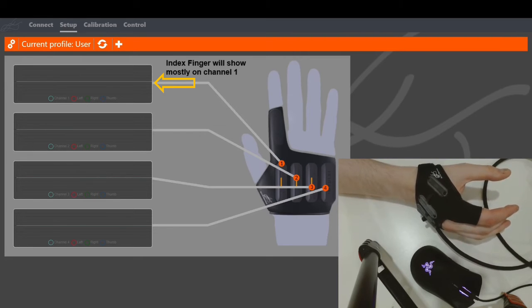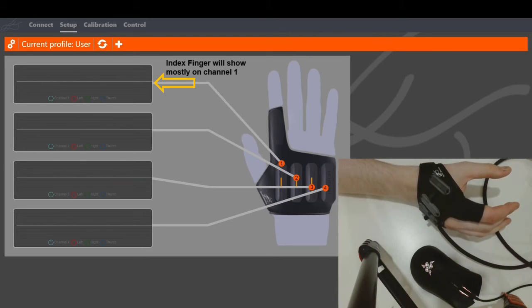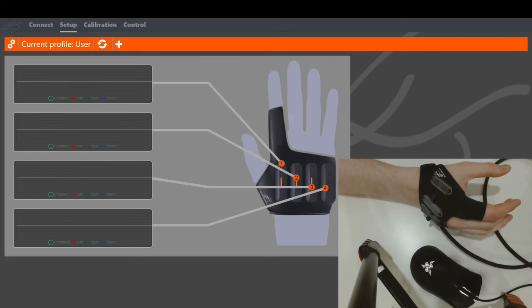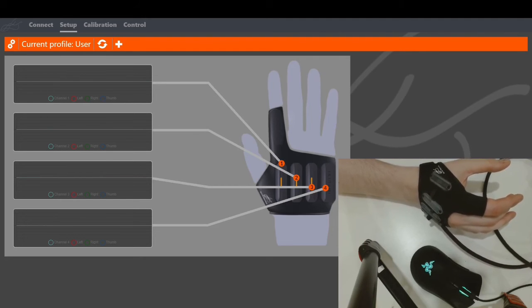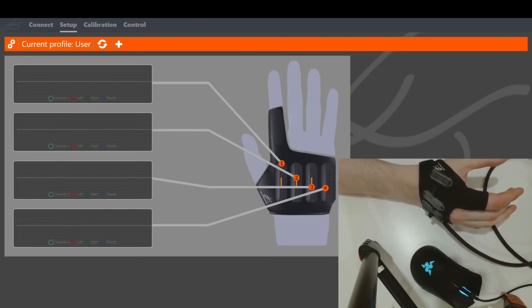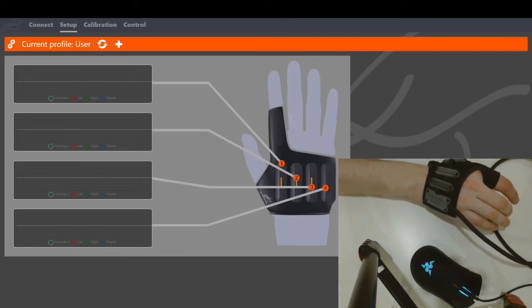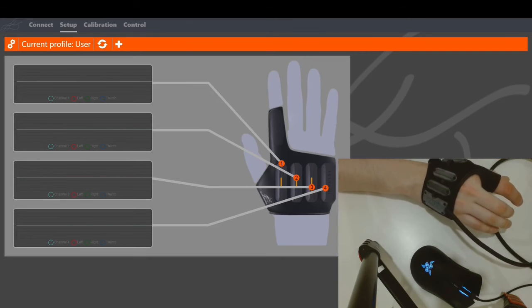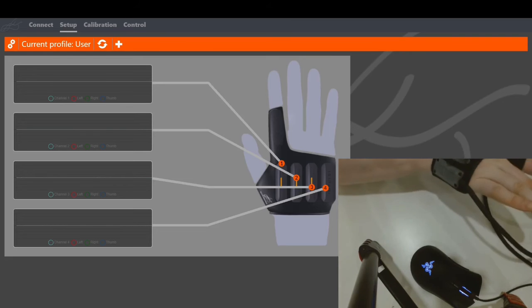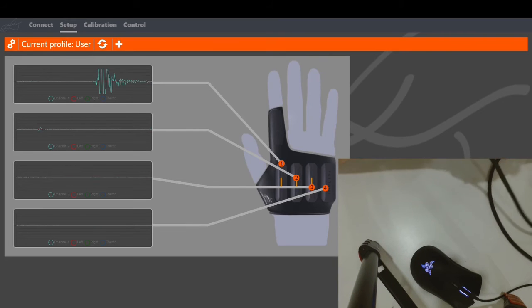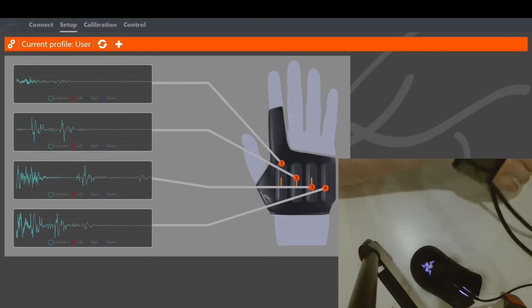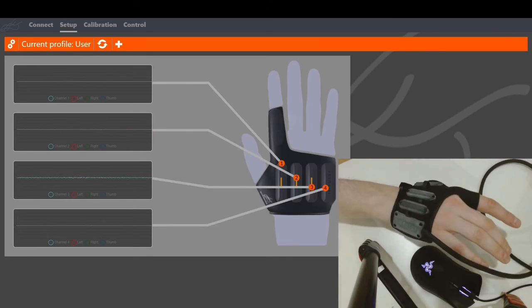If you can see a difference between the muscle activity when you're moving and the background noise when you're relaxed, then so can Impulse. If you can't see a difference between these two, that is, you're not getting much activity when you're moving, then Impulse likely won't be able to tell either. This is your first sign that you need to find different electrode placements, and it may even be a movement of just a few millimeters. So if I move Impulse on my hand far over, where the electrodes are no longer in the right spots, this is an incorrect alignment.